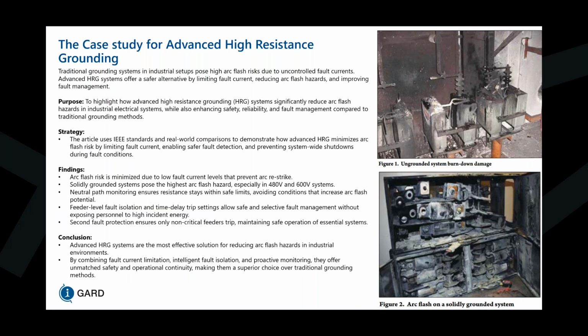So advanced HRG systems offer a safer alternative by limiting fault current, reducing arc flash hazards, and improving fault management. The purpose of this case study is to highlight how advanced high resistance grounding systems significantly reduce arc flash hazards in industrial electrical systems, while also enhancing safety, reliability, and fault management compared to traditional grounding methods. This article uses IEEE standards and real-world comparisons to demonstrate how advanced HRG minimizes arc flash risk by limiting fault current, enabling safer fault detection and preventing system-wide shutdowns during fault conditions.